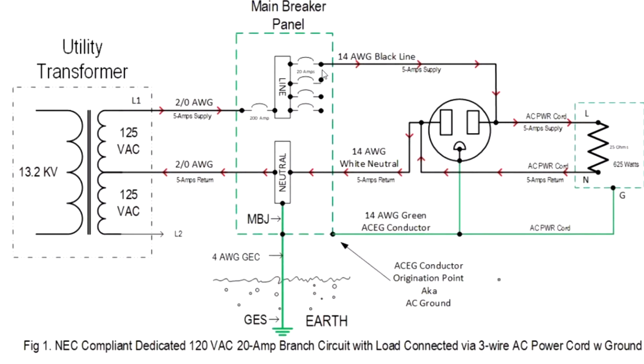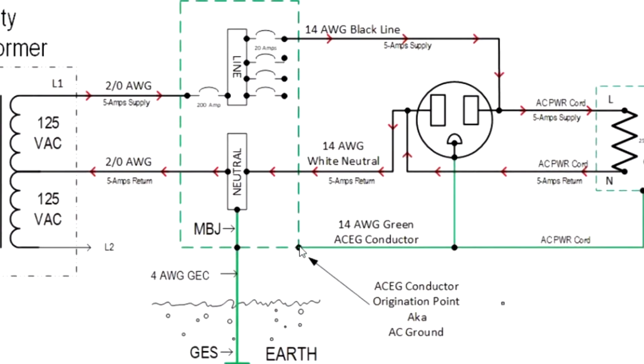In your meter panel, the neutral, or the center tap from the transformer, is the neutral conductor. It will come into either your meter can or your meter panel, depending on how it's laid out. You're going to have the ground electrode system with a ground electrode conductor coming up, and it's going to be solidly bonded to that neutral. It'll also be solidly bonded to the service can, or your breaker panel, excuse me. Then from your breaker panel, we go out to distribution.